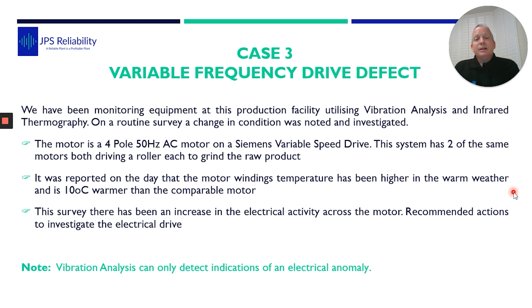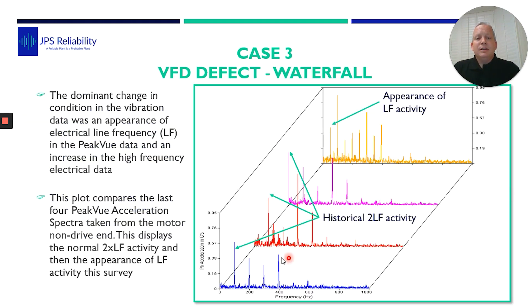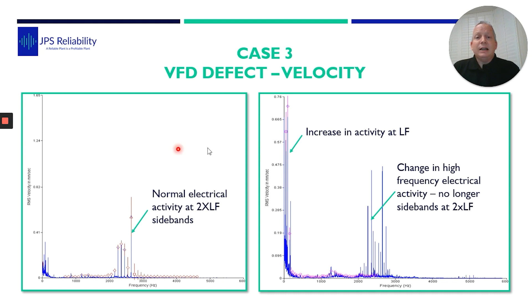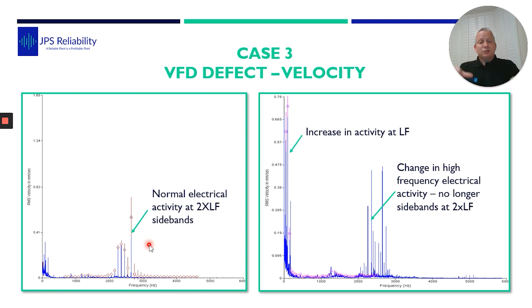This is the vibration data, and down the bottom here is the historical data where you can see the two times line frequency. On this particular survey, we suddenly had an appearance of a one times line frequency — 25 hertz — which is really abnormal. This is the PeakVue data. Comparing the velocity, the normal velocity levels actually came down, but what you'd normally see is the two times line frequency, whether that's from an eccentric difference in the air gap or it's been torqued down, or just natural motion. On this survey, we had a large increase of 25 hertz, and the electrical mount was now actually side-banded by 25 hertz. So the vibration had increased, but there was a change in the pattern and the condition.